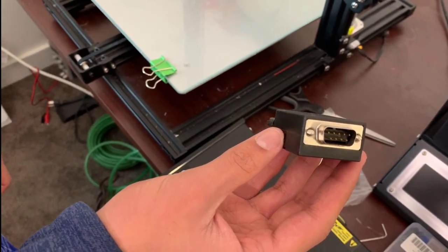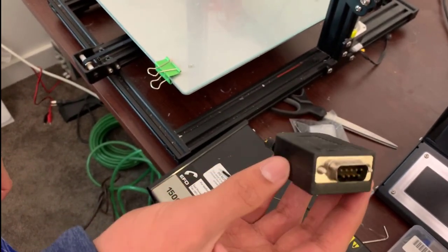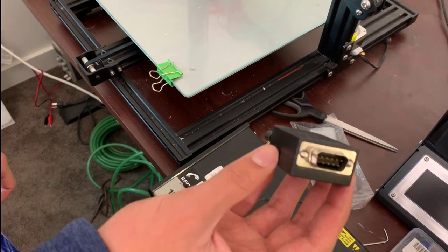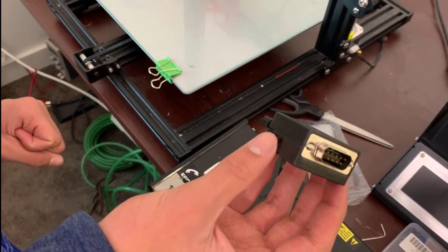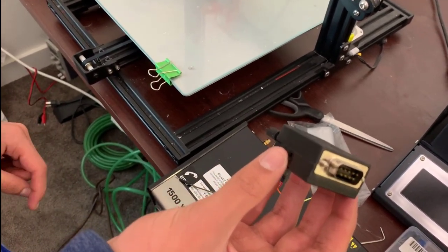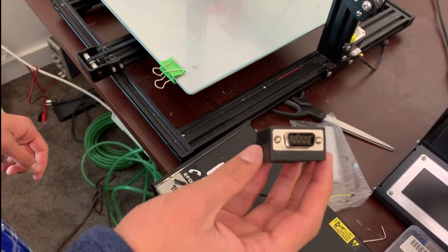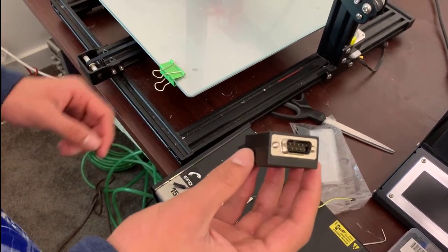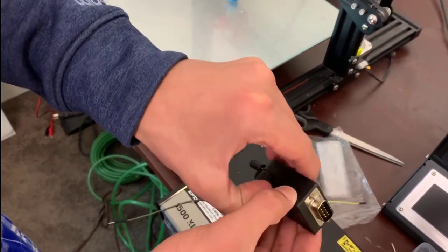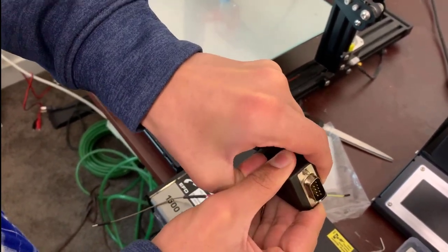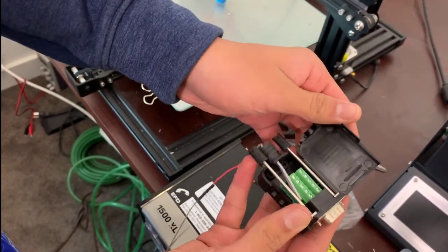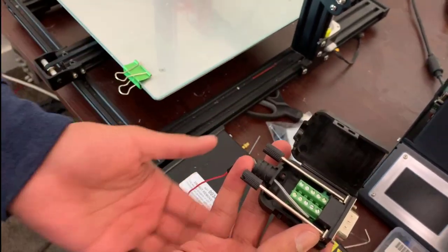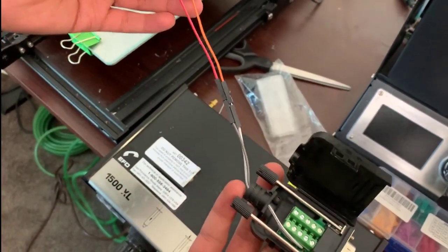And so what we're going to do is we are going to connect two leads to the two pins that actually power the valve in the EFD dispenser. And in this case, those are pins 1 and 2. And so what we do now is we're just going to open up the actual connector and we're going to connect the two leads to the pin out port.